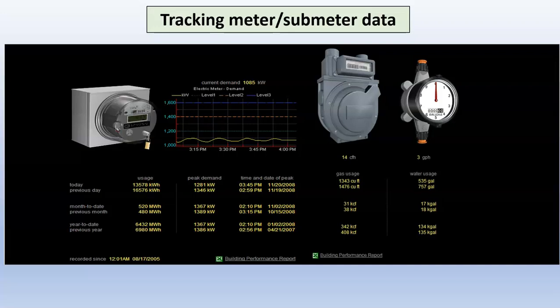Submeters, great to track this data. I can tell you as an energy guy that if they have a submeter and they're tracking it, that's probably the single most powerful tool so far as energy auditing goes, because they can tell me that they're shutting down at night, that they're shutting down on the weekends. But when I see the graph of kW versus time, I know what they're doing. If it's not dropping down on the weekends, I know that maybe they say they're shutting down, but maybe somebody snuck in and turned it back on, or you can really see the story. And then you can start making changes in the system. You can shut a bunch of stuff off to see what the kW is. Then that's where you should be on the weekends. You can really get down into the nitty gritty, troubleshooting why the energy use is higher than it should be with tools like this. Very powerful.